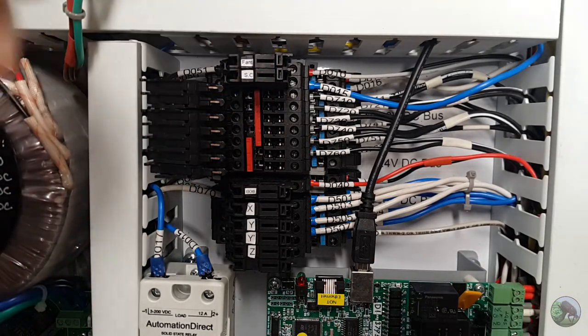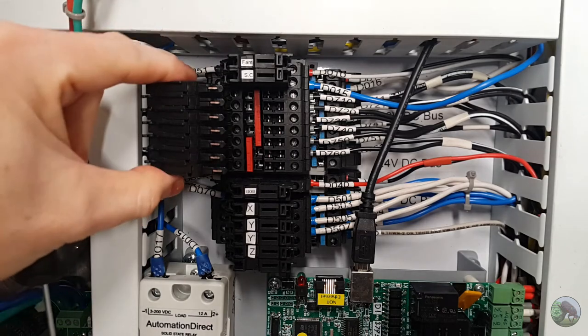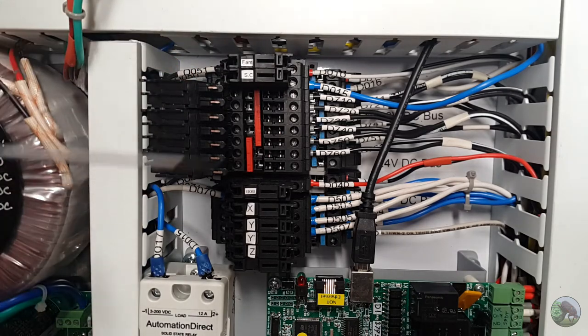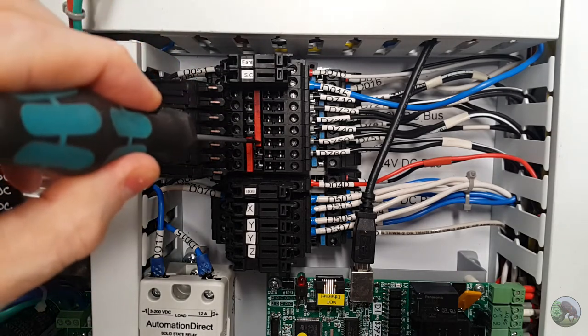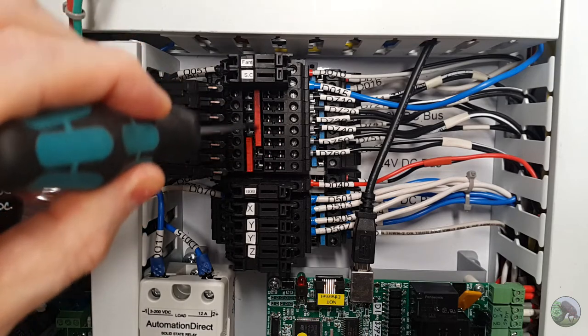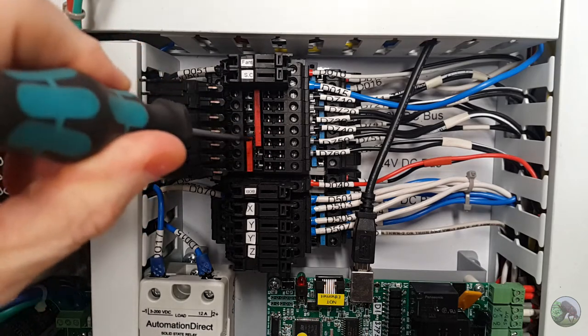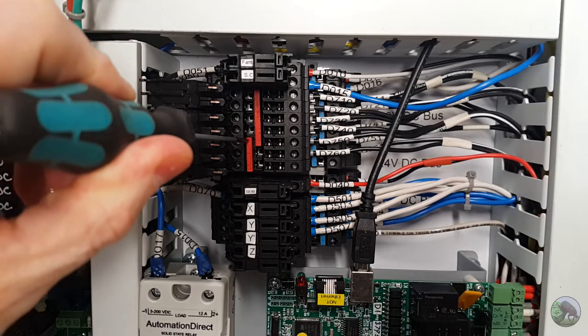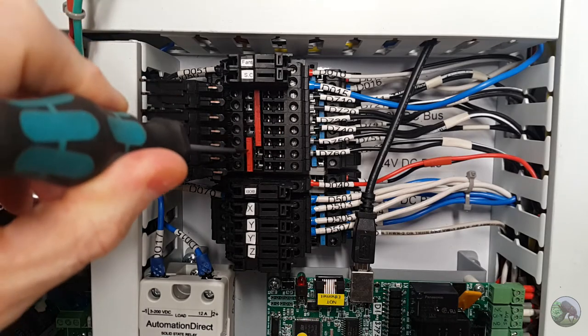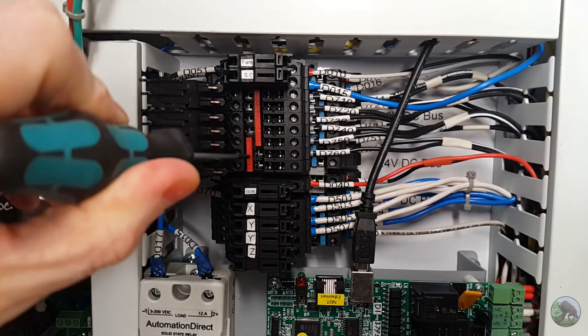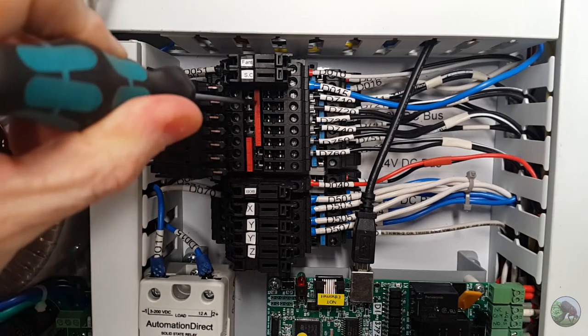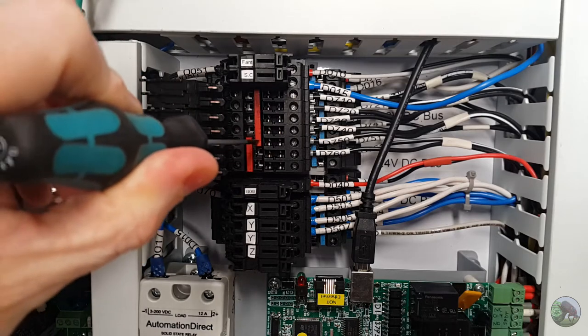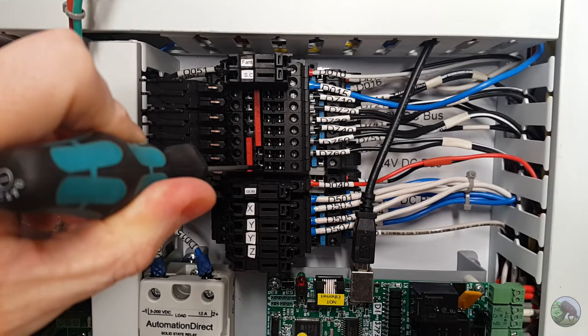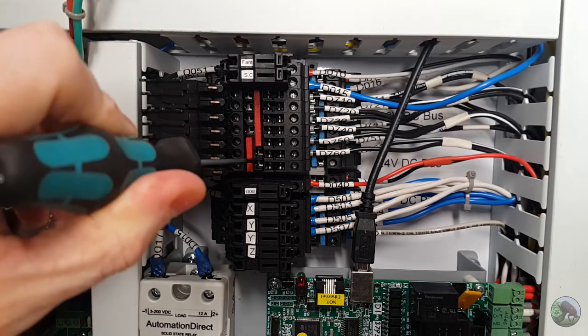But anyway, now the next seven terminal blocks are all for sensors on my machine. As you can see here, they're bound together with these bridges. It's good to point out that's the utility of having two rows of bridge connecting points. If I didn't have two rows, I couldn't do this, and I would have needed to have a bridge that was exactly the right length.